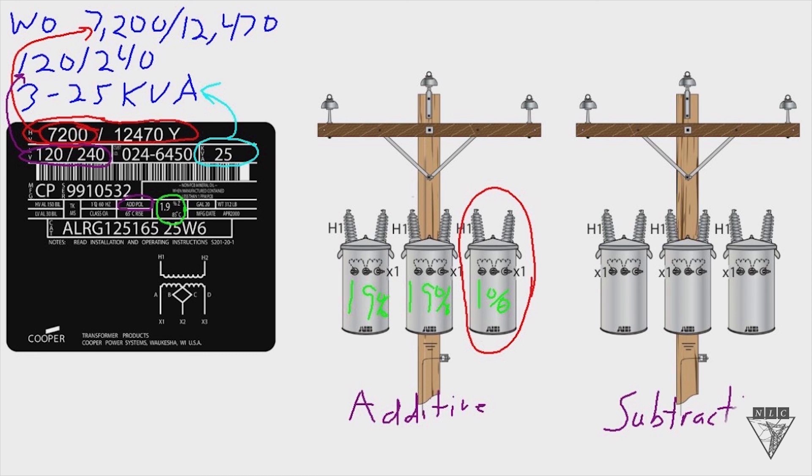Okay, so that's the criteria for choosing the right transformers, single phase transformers when banking or paralleling transformers. You need to know the circuit voltage, the service voltage, the size transformers you need, and then try and get the polarity to match and try and get the impedance as close as possible for all three.